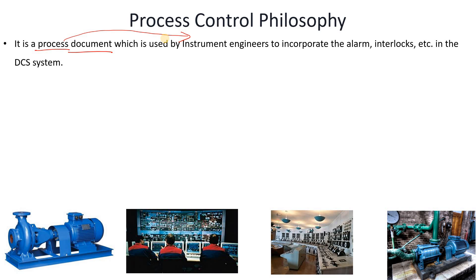For example, as a process engineer you have prepared a P&ID with a pump. You have provided two interlocks: first, if the tank level goes low-low, the pump should be tripped; second, if the discharge pressure of the pump goes high-high, the pump should also be tripped.